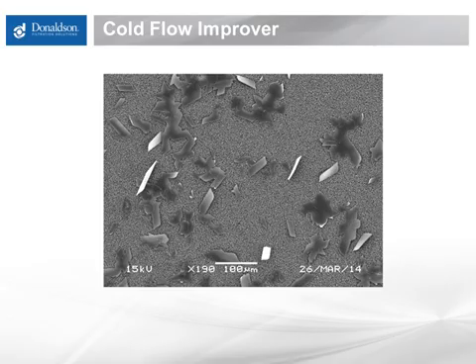It is a fact that No. 1 diesel, with its shorter chain hydrocarbons and lower cloud point, will likely perform better in colder weather than No. 2 diesel. Many effective strategies for dealing with cold weather problems call for increasing the percentage of No. 1 diesel in the fuel. It is especially important in newer equipment, where the highest quality cold flow improvers can contribute to the plugging of high-efficiency filters. However, No. 1 diesel is considerably more expensive than No. 2 diesel. In addition, No. 1 has less heat content than No. 2, which can have an impact on fuel economy. Whether you're thinking of using a less efficient filter, increasing the percentage of No. 1 vs. No. 2, or modifying your additive doses, it's important to get expert advice.